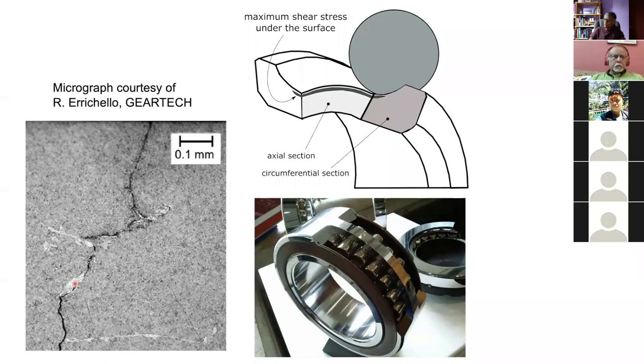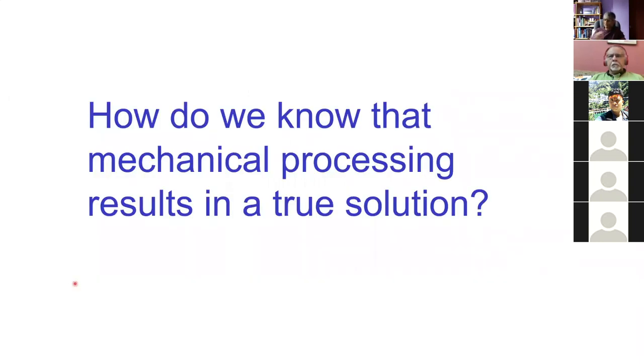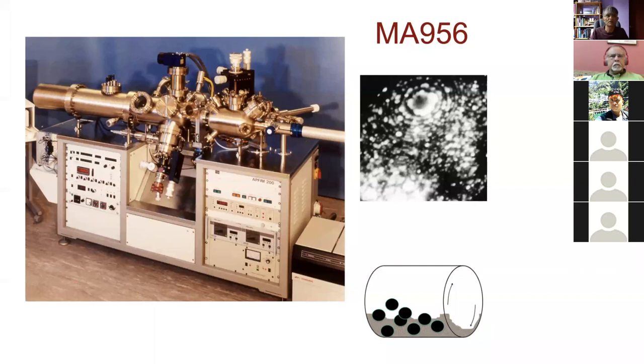How do we know that mechanical processing leads to a true solution? The obvious method is an atom probe field ion microscope. You have a very sharp tip of the material, apply a very large electrical field, and an imaging gas ionizes when it touches an atom, spreading out in the electrical field to give a magnification of about 10 million. Here is an image from mechanically alloyed material where each dot is an individual atom. You also have a time-of-flight mass spectrometer so you can pull out an atom, measure its flight time, and get chemical information per atom.